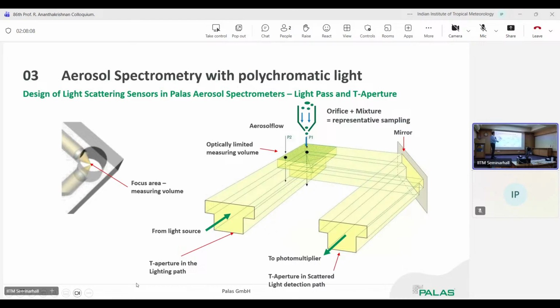So with this T-shaped cutout in front, we can make it even more narrow, and then we only analyze a small portion in light scattering, compared to when the T is wider. Light scattering then takes place only in a smaller area. If you have high concentration, you typically do not need to analyze everything. Statistically, it must be representative. By narrowing this area with the T-shape, or by opening it completely, we can tune the system: more light scattering and more particles measured, or less light scattering and fewer particles measured.